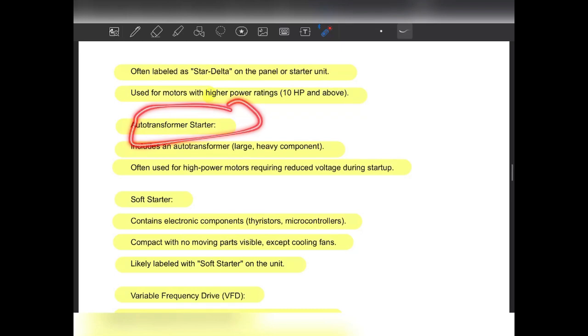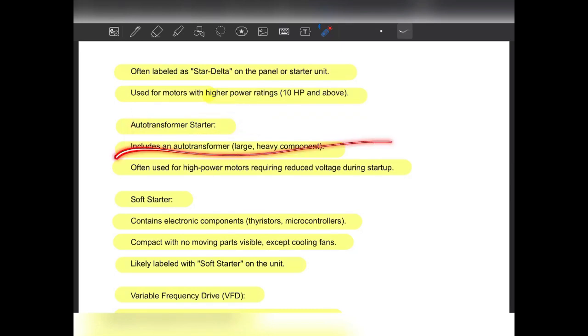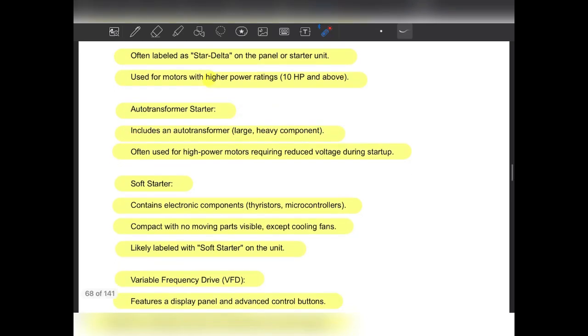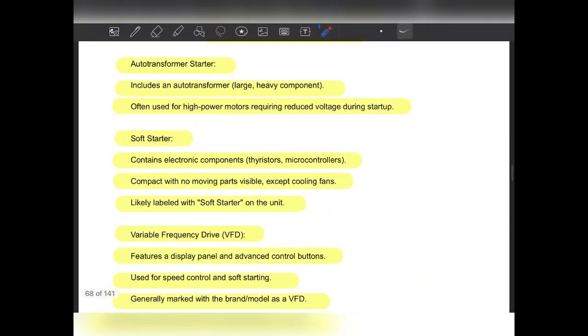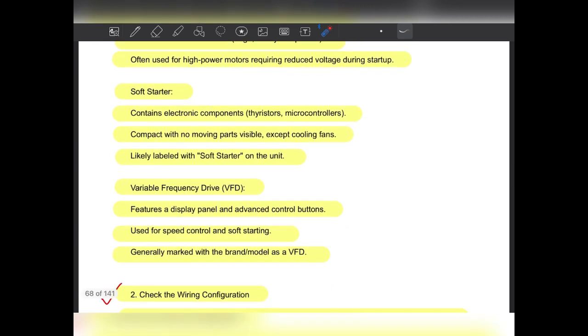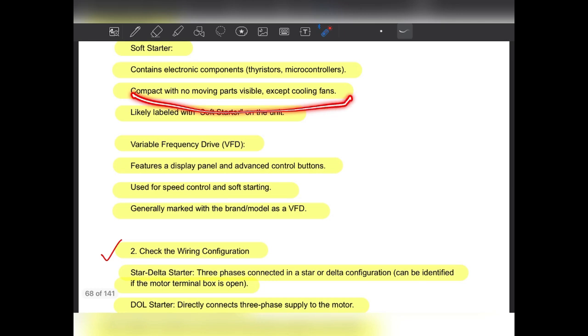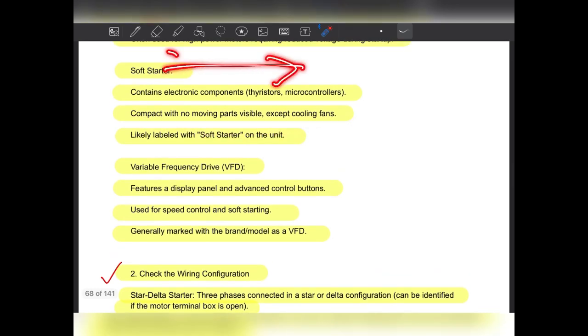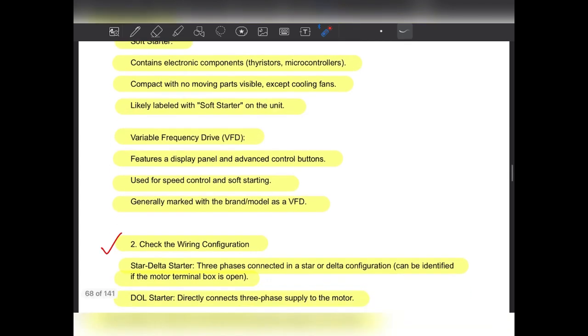Sometimes an auto transformer is a very bulky and heavy component, so you can easily tell if there is an auto transformer. A soft starter is basically an electronic device, so you can easily recognize it. It has electronic components like a thyristor and a microcontroller, no moving parts inside, and there is a bypass also. If you want to bypass the soft starter, you can easily bypass it. A variable frequency drive basically varies the frequency and voltage. It has a display panel, is used for speed control, and you can also check with the help of the wiring diagram.